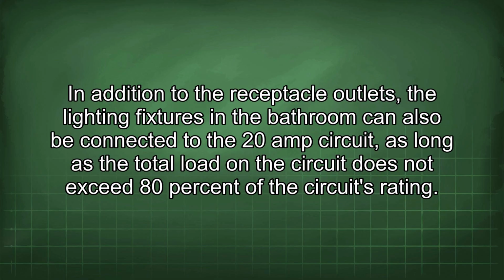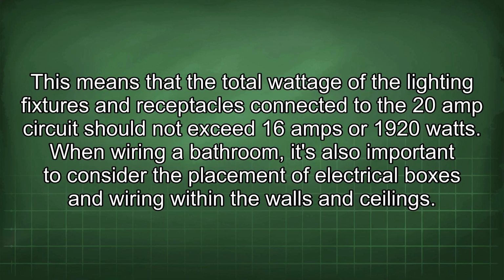In addition to the receptacle outlets, the lighting fixtures in the bathroom can also be connected to the 20 amp circuit, as long as the total load on the circuit does not exceed 80% of the circuit's rating. This means that the total wattage of the lighting fixtures and receptacles connected to the 20 amp circuit should not exceed 16 amps or 1920 watts.